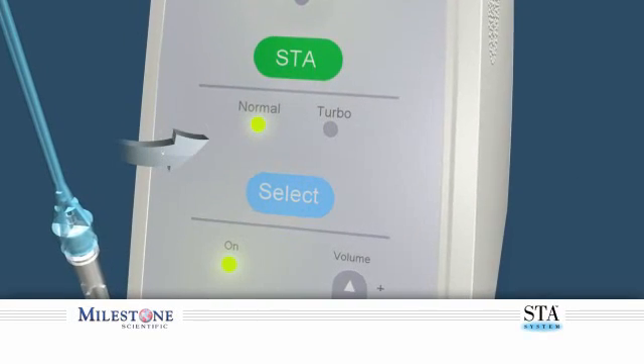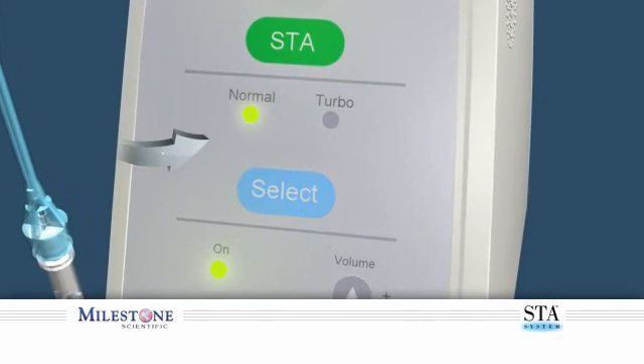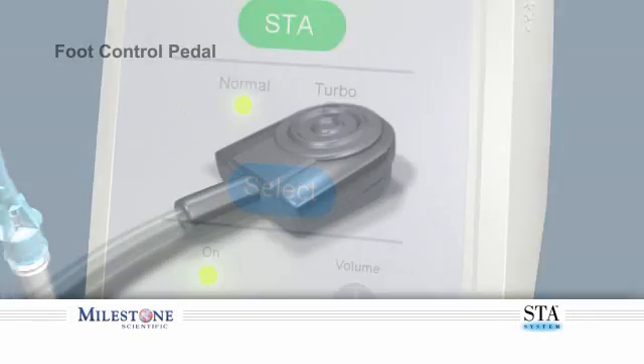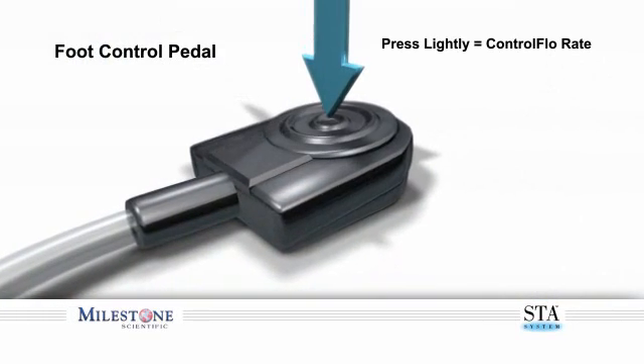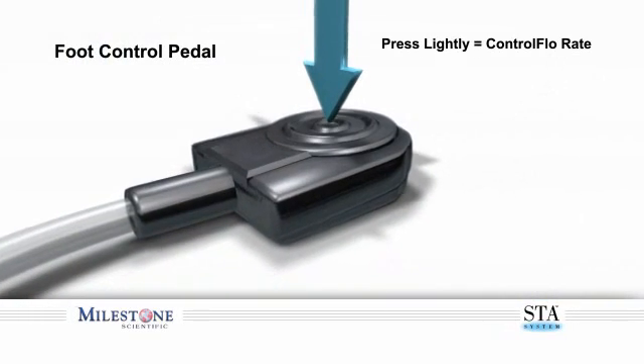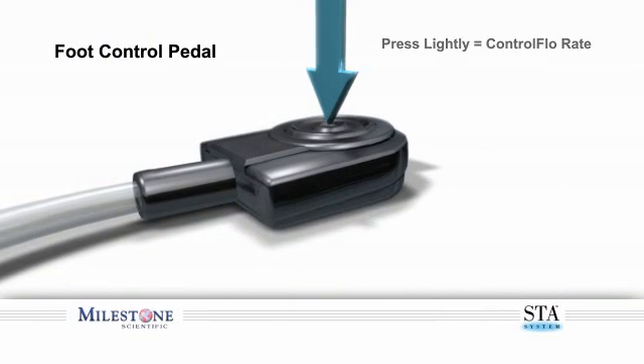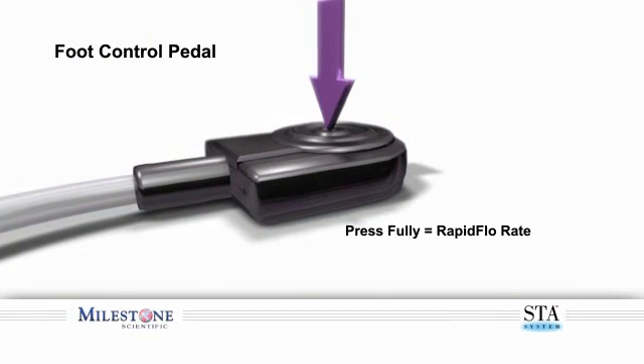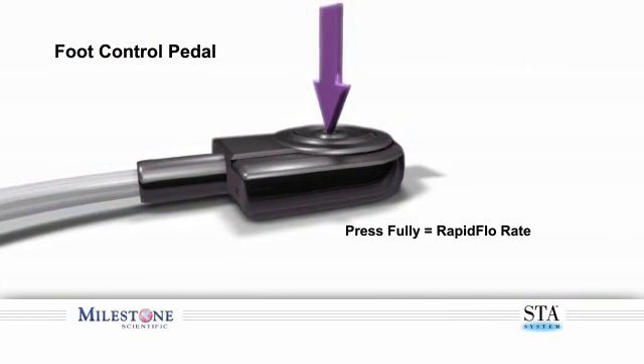In the normal mode, the foot control has two distinct foot control positions. Depressing the foot control lightly allows you to enter the ControlFlo rate. Fully depressing the foot control allows you to enter the RapidFlo rate.